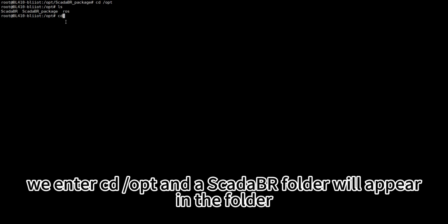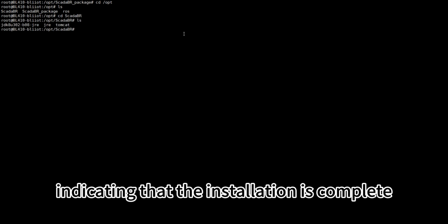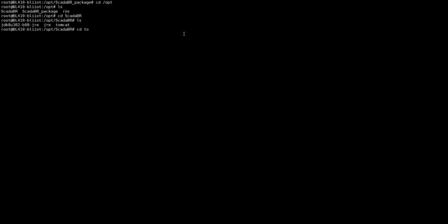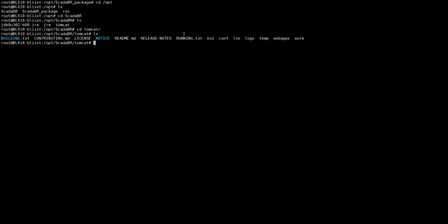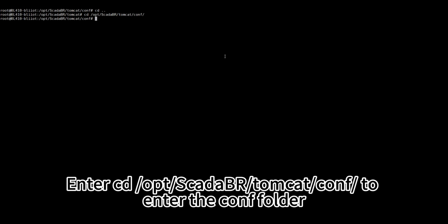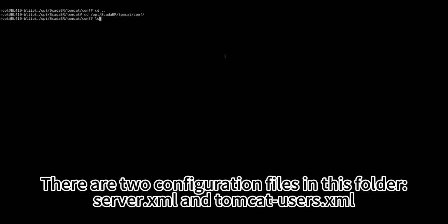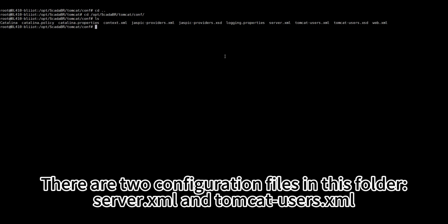After the installation is complete, we enter cd /opt and a SCADA BR folder will appear, indicating that the installation is complete. Enter cd /opt/ScadaBR/tomcat/conf to enter the conf folder. There are two configuration files in this folder: server.xml and tomcat-users.xml.